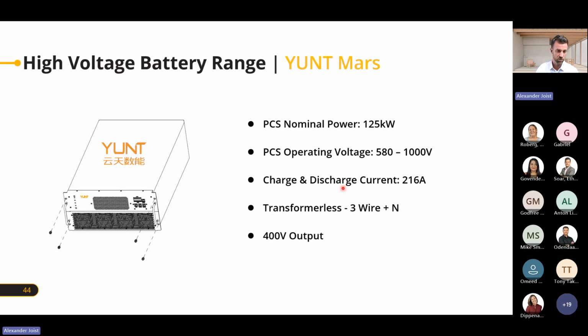So you can run it without a transformer, but just make sure it's a very balanced system and we don't have any high inductive loads or anything like that starting up on that system. If we do that, please make sure you install a transformer for the harmonics of the whole system and to make sure for longevity of the PCS, right? That's quite important. But other than that, if you can take 2 or 3 of them and parallel them, you don't need a transformer. So it's a very, very, very cost efficient solution.